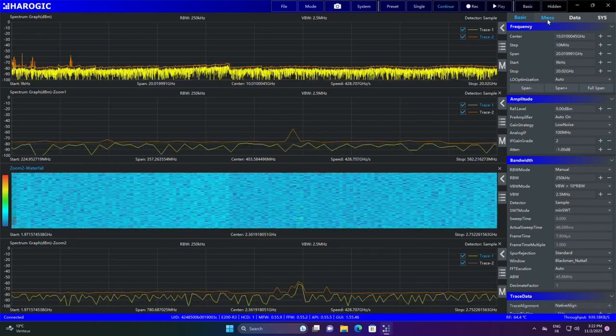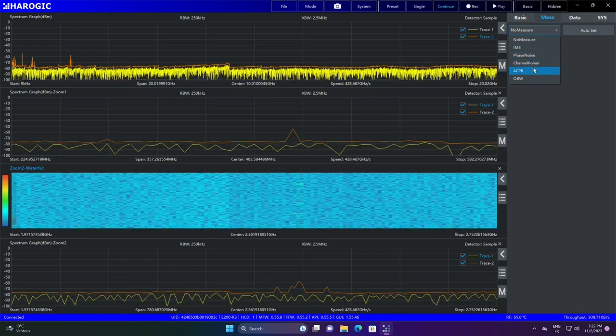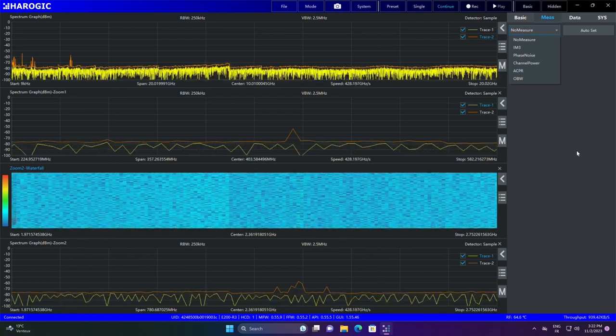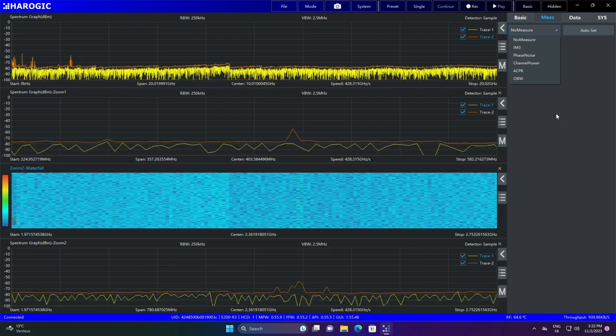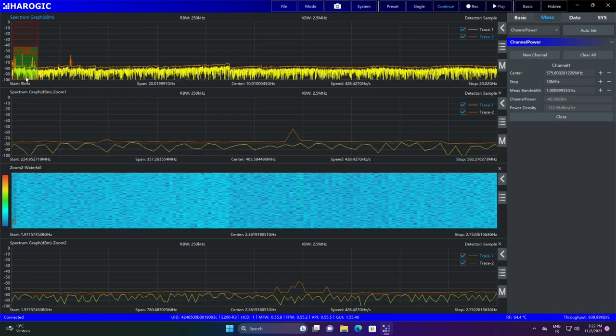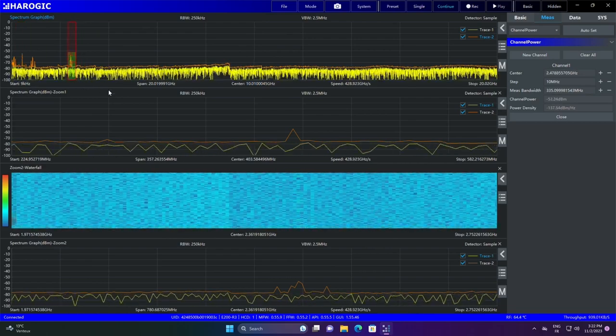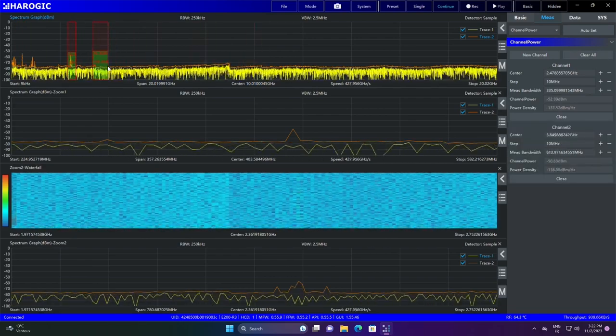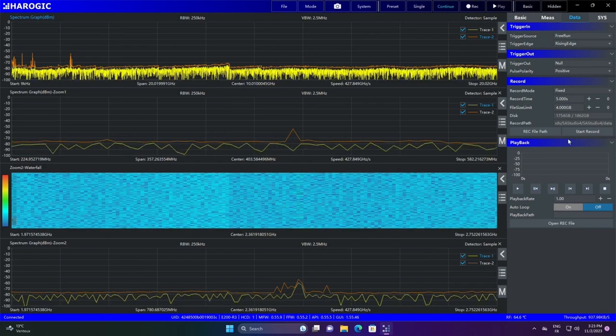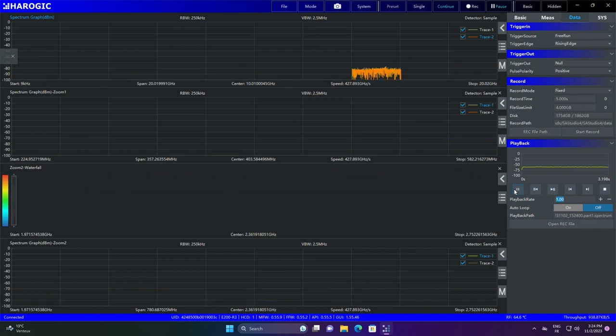There are also measurement tabs: IM3, phase noise, channel power, ACPR — a lot of features, though fewer than in Spike software. You have channel power measurement where you can specify a channel and measure its power. There is also a data recording feature — you can record what is happening right now and replay it afterwards.